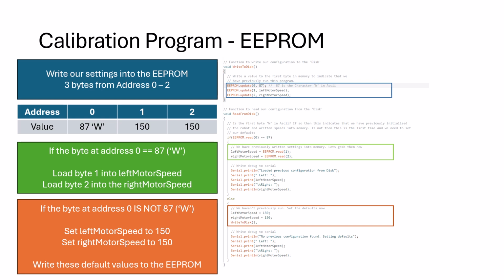Now notice that once we've done that in this read from disk function, we then write to disk those basic calibration settings to ensure that we have something written in the memory. It's now basically set up and ready to go. Both values are set to 150. It won't be calibrated at this point, but the next step will be to actually run that calibration process.